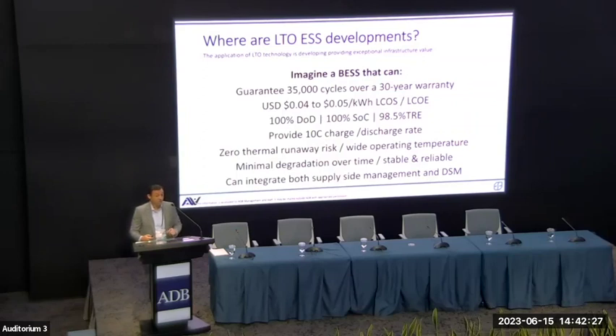It also provides up to 10C charge discharge, meaning a 1 megawatt hour battery can charge or discharge in 6 minutes. It has zero thermal runaway risk, so the battery cell cannot explode. It has a wide operating temperature range, between 10 to 70 degrees Celsius, providing minimal degradation over the life of the product. It's stable and reliable.